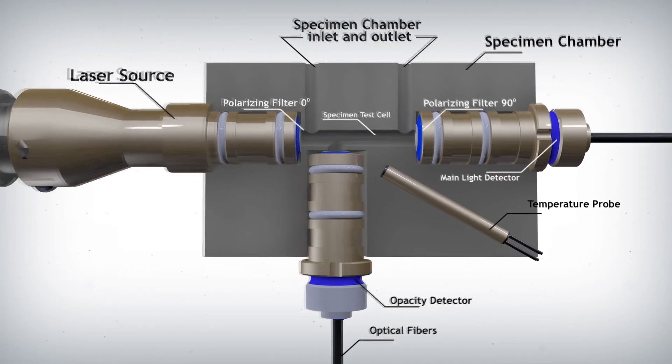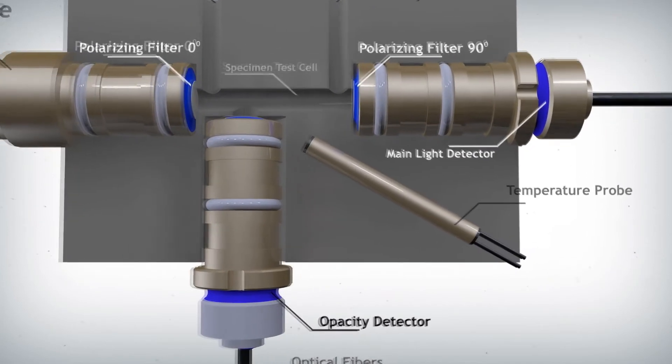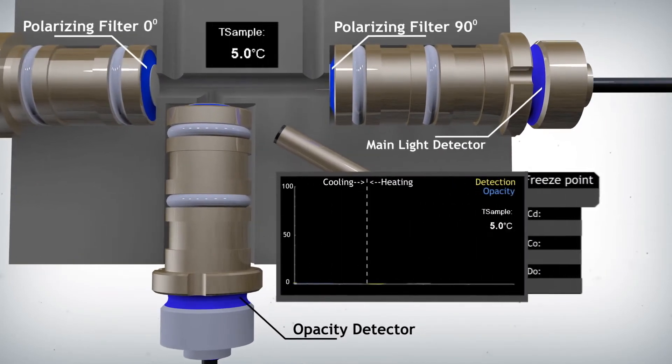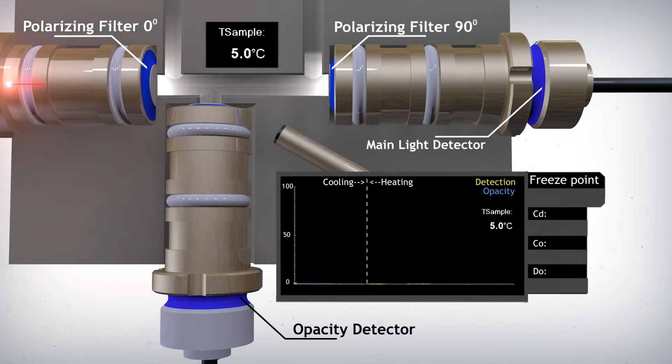Let's see how the detection system works and how the detection signals are displayed for neat jet fuel. As we zoom in on the thermal block, we superimpose the actual temperature and the resulting graph. The sample fills the specimen chamber and the laser turns on. In this example, the test starts at 5.0 degrees and continues cooling.